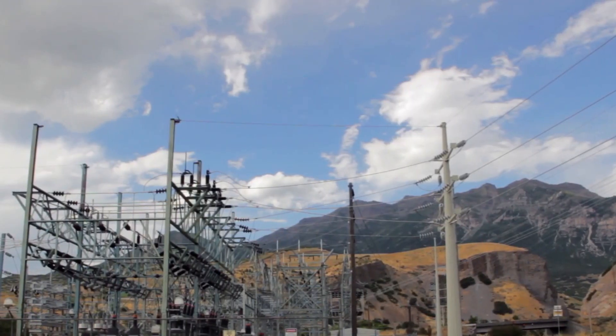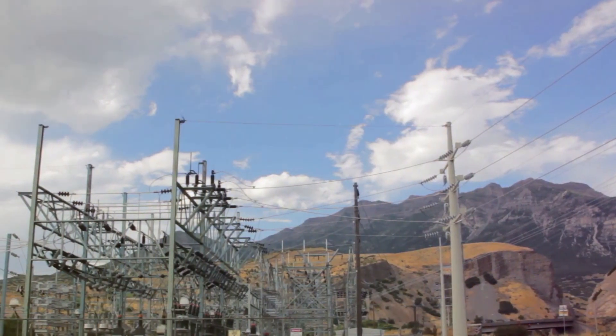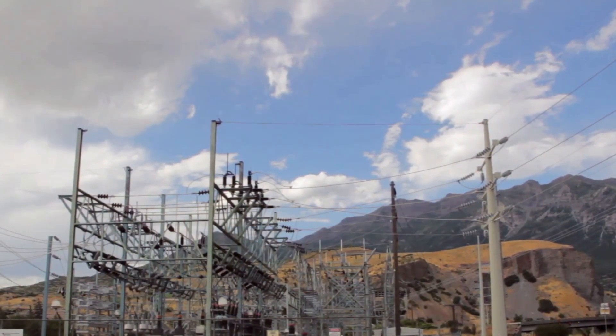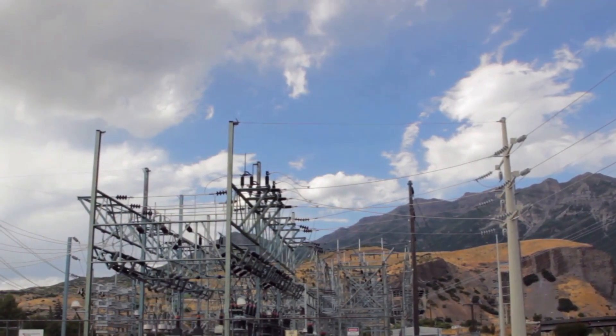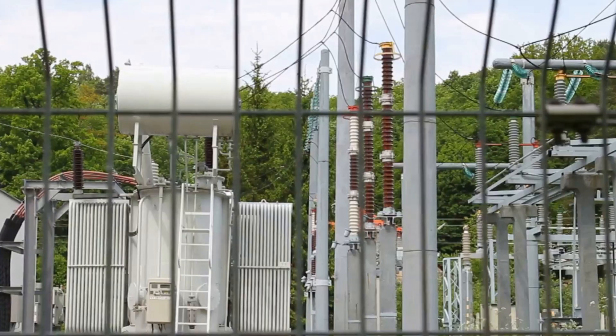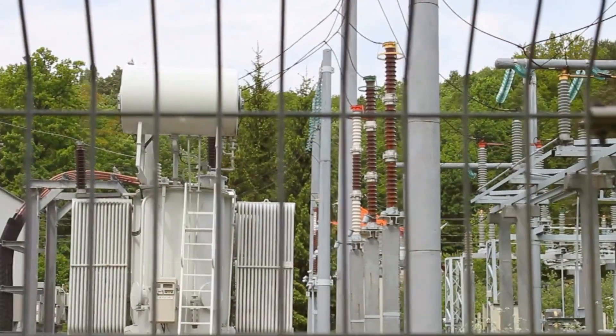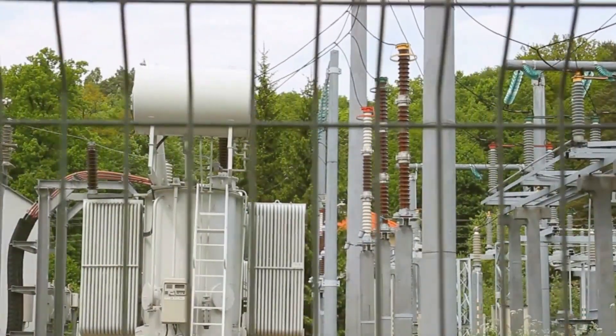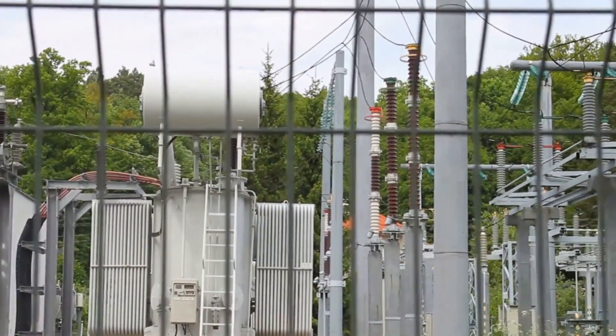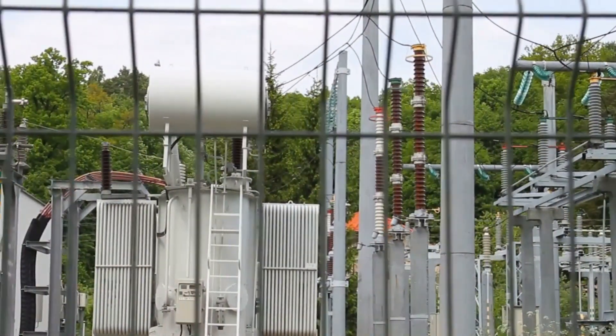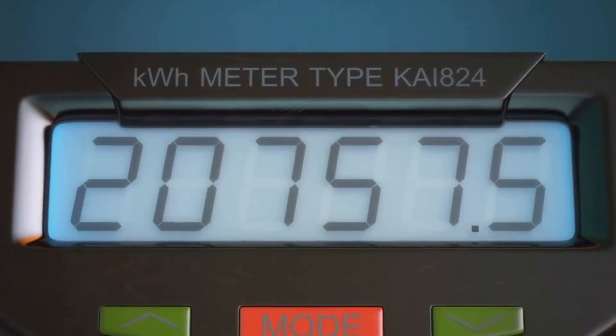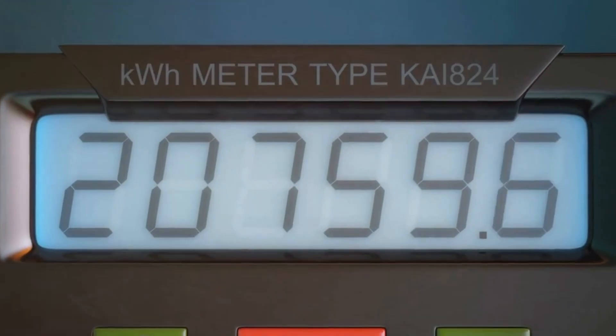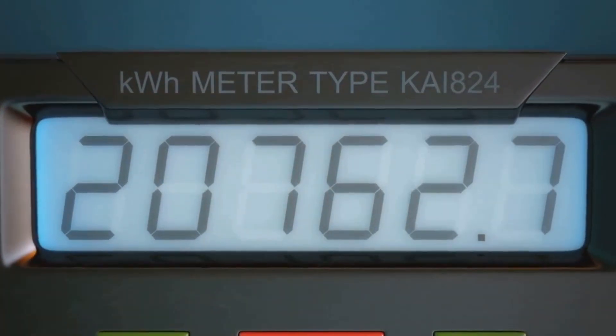So, to sum up: a transformer is rated in VA or KVA because its losses depend on both voltage and current, irrespective of the load power factor. This rating provides a more accurate representation of the transformer's capacity and ensures its efficient and safe operation. Remember, in the world of transformers, it's all about the voltage and the current — and that's why we rate them in VA.